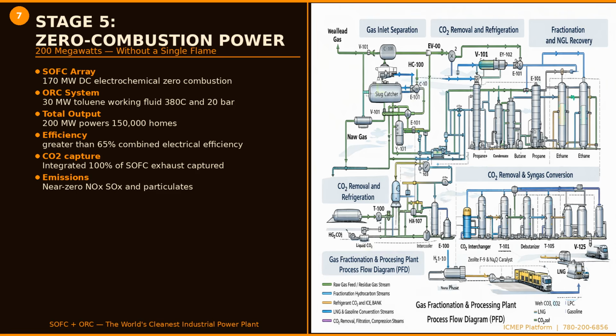This is where the ICMEP platform makes history. 200 megawatts of clean electricity, generated without burning a single molecule of fuel. The Carbon Managed Energy Recovery Center uses solid oxide fuel cells, the most advanced power generation technology ever deployed at industrial scale, to electrochemically convert methane directly to electricity at temperatures between 700 and 900 degrees Celsius. 170 megawatts of DC power flows from the fuel cell arrays. The high-temperature exhaust then drives an organic Rankine cycle system, extracting an additional 30 megawatts from what would otherwise be waste heat. 200 megawatts total.